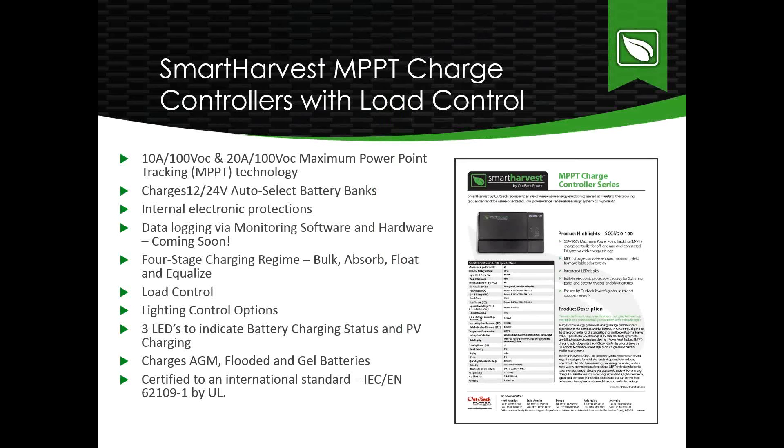Now for the products themselves and features. We've launched 10A and 20A Maximum Power Point Tracking charge controllers. Both can take up to 100 volts open circuit from the PV array and auto-select 12 or 24 volt battery banks. They include internal electronic protections — for instance, if someone reverses terminal connections on the battery bank or load. Data logging capabilities are coming soon as we work on new monitoring software and hardware. The Four-Stage charging regime includes bulk, absorb, float, and equalize — equalize applying for VRLA-type battery banks.